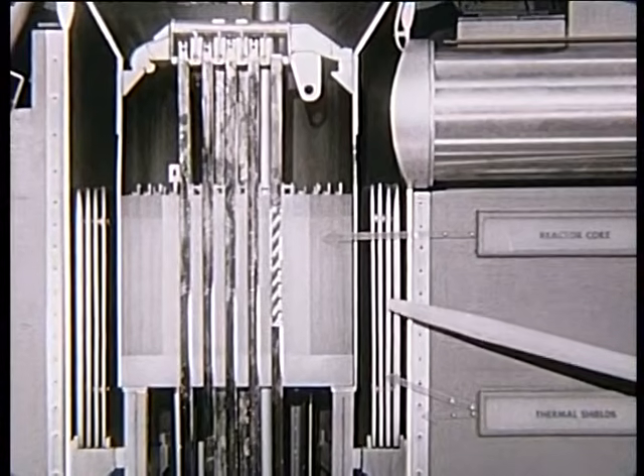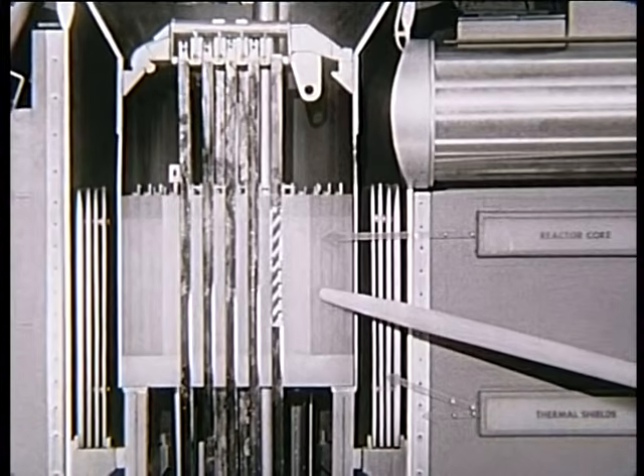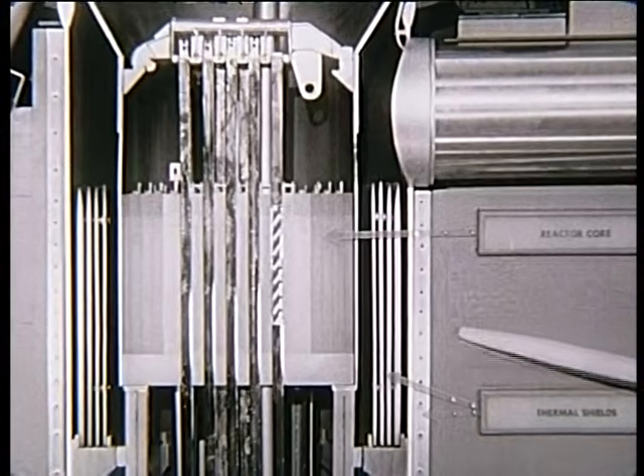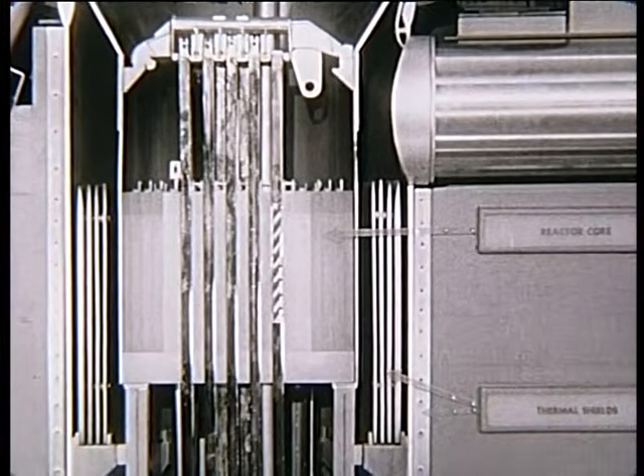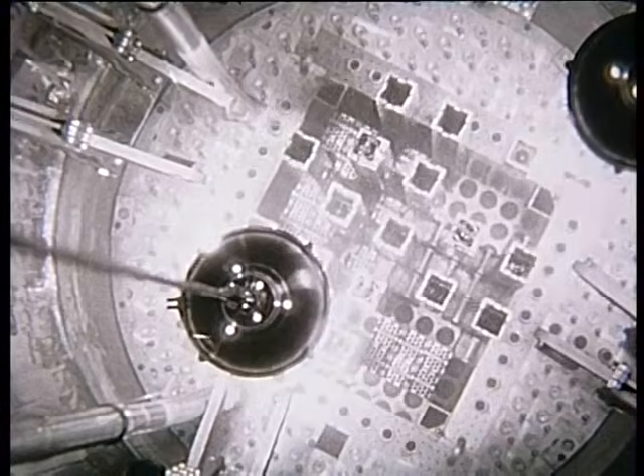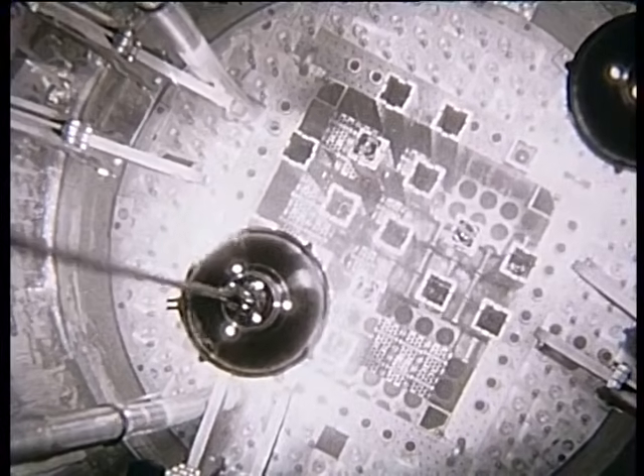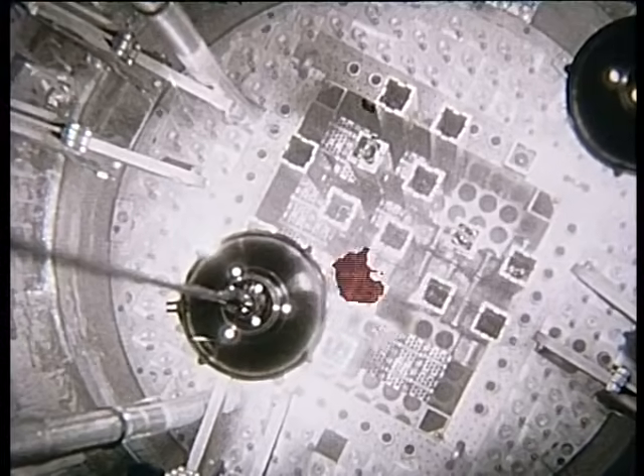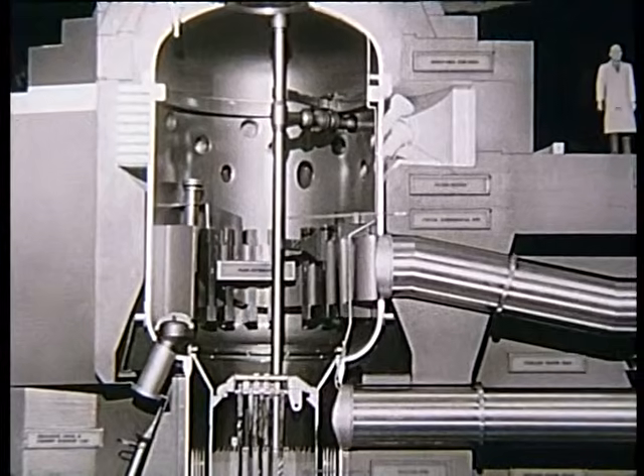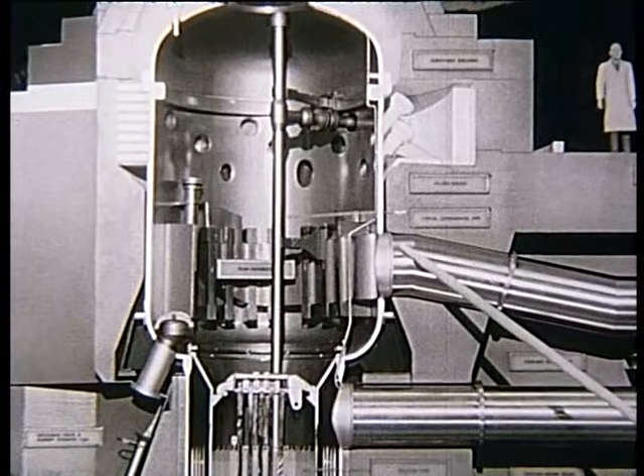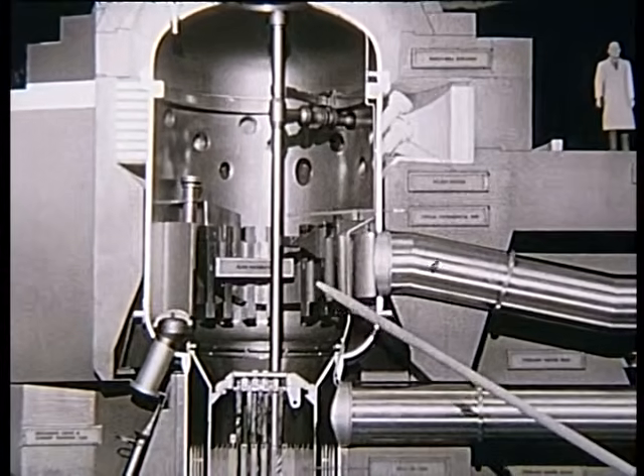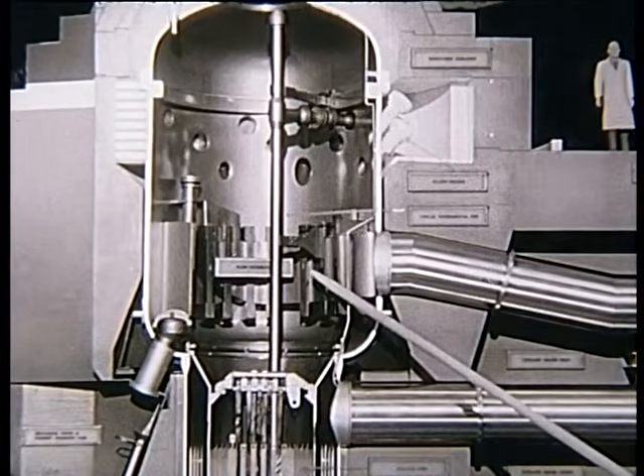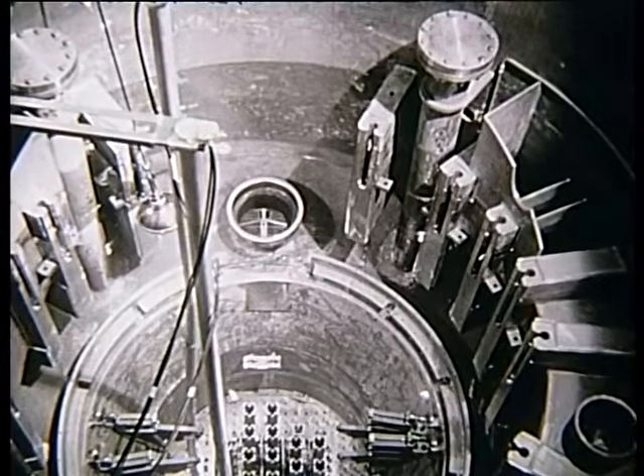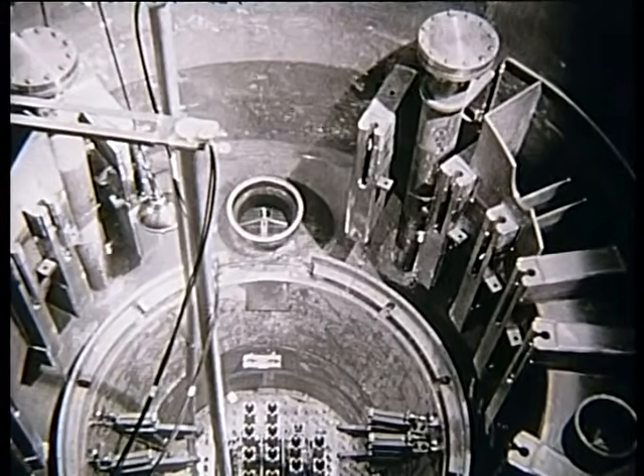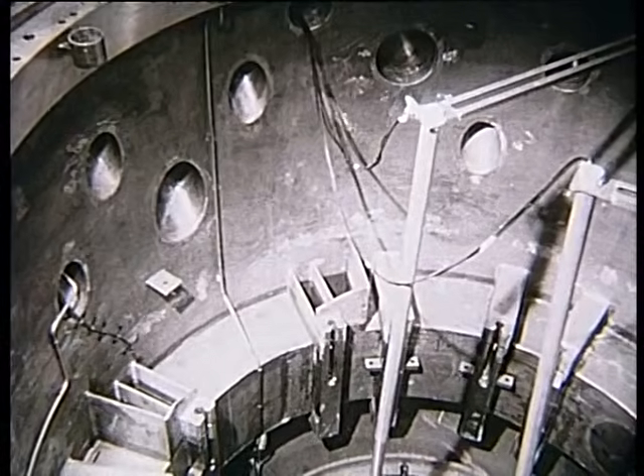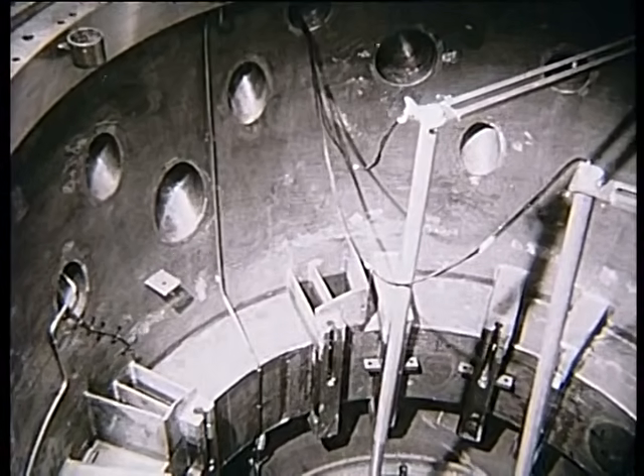The external and internal thermal shielding surrounds the core area in general and will serve to limit the temperature at the inner face of the concrete biological shield to 120 degrees Fahrenheit. The reactor is cooled by demineralized water flowing at about 44,000 gallons per minute, or at 35 feet per second, through the core area. It enters the reactor through a 36-inch pipe in the upper vessel. The water is then deflected upward by a flow distributor. The distributor, by changing flow direction, minimizes turbulence and hydraulic loads on internal installations and acts to dissipate input vortices and vibrations from the pumps.